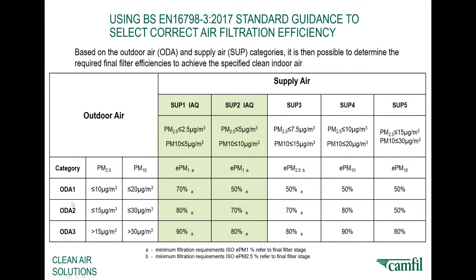So if we want a good ODA2, which is your general purpose office type environment, and you want a good SUP2, should I say, indoor office environment, SUP2, and you've got an outdoor city environment, which would typically be ODA3. So you'd come across from ODA3 on the horizontal axis there and cut across the SUP2 in order to have the required filtration to come from that level, the dirty level of outside air, down to the clean level of inside air required.